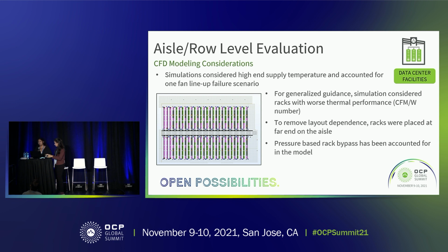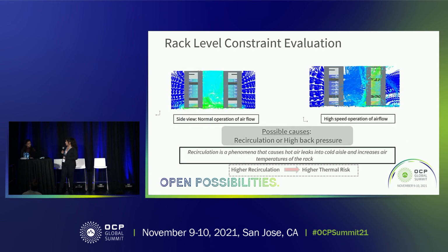Thank you, Jayati. When we did the aisle level evaluation, we did not see any high-risk thermal impact on our racks. But what we saw is that in our hot aisle, we saw localized pressurized spots. So we wanted to investigate what that could mean at the data hall scale. So we have done CFD modeling focusing at rack level, where we model 2 rows that would share a hot aisle. And during normal operation, this is what we expect. We are looking at 2 rows from the side. The cold air is entering the racks, and now the hot air is being exhausted towards the ceiling.